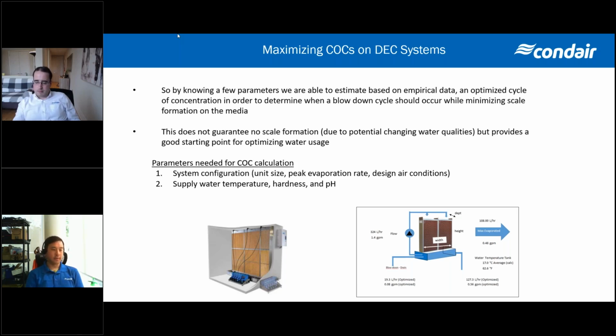And then in terms of temperature, the colder the water, the better. That helps us operate in a non-scaling mode with a maximum temperature of about 24 degrees Celsius, primarily just for hygiene reasons, because as we get higher than that, it really starts to promote the growth of bacteria in the water system. So just a few things to keep in mind.